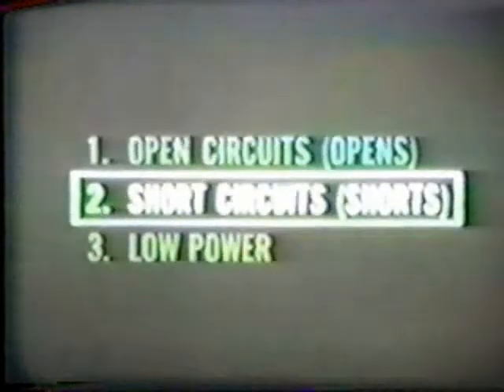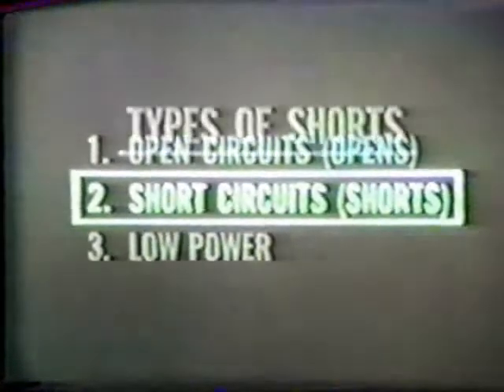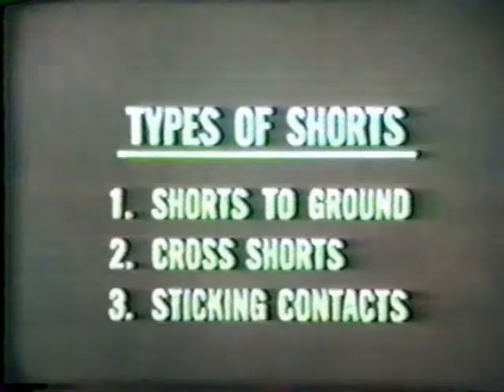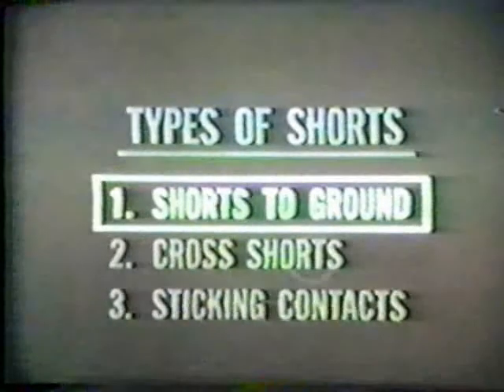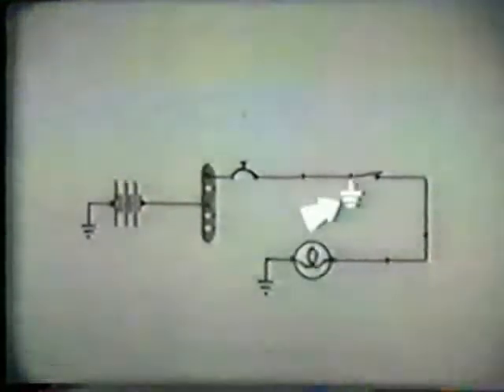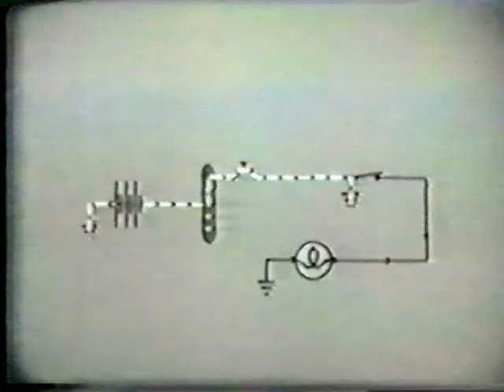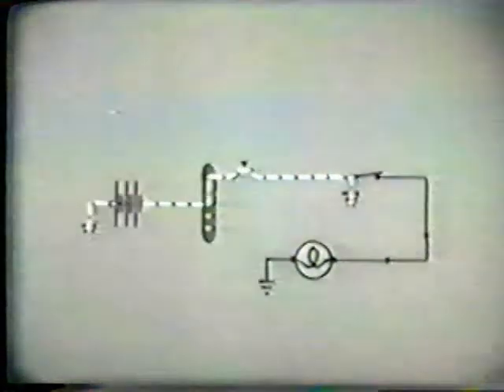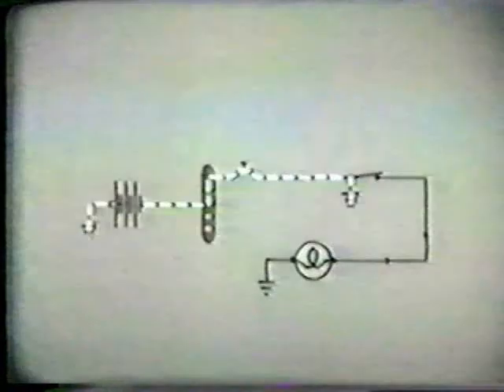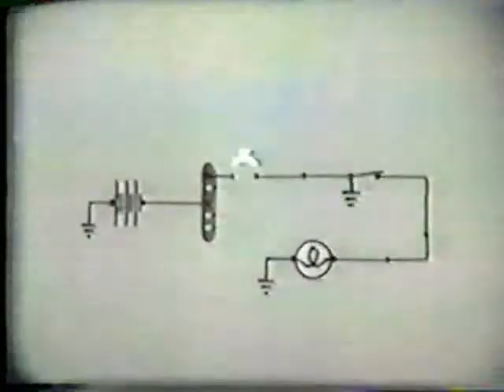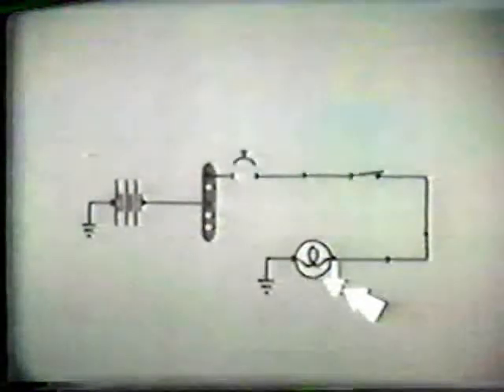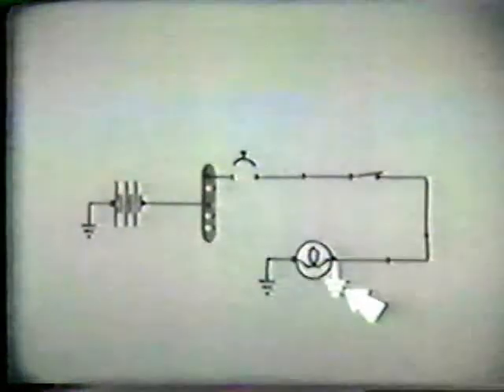We are said to have a short when current flows in paths other than those intended. Actually, there are 3 common types of shorts: shorts to ground, cross shorts, and sticking contacts. Shorts to ground cause a circuit to fail by grounding the circuit before the using unit. Current follows this short path, and part of the circuit becomes inoperative. When a short to the ground occurs, the circuit breaker or fuse will normally open to protect the circuit. This results in a stopping of all current flow. Shorts to ground can occur in any of the units of a circuit or in the wire connecting the units.